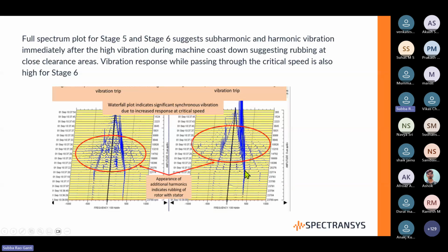And then after the machine trips, when the machine is coasting down, if you look at the cursor on the right side, you can see that at a certain speed the amplitudes of the vibration forward components have drastically gone up. At the same time, you can see some reverse components coming into the picture. And on both the forward and the reverse side, you can see some harmonic content coming into the picture. This harmonic content did not exist before and after those high spikes.